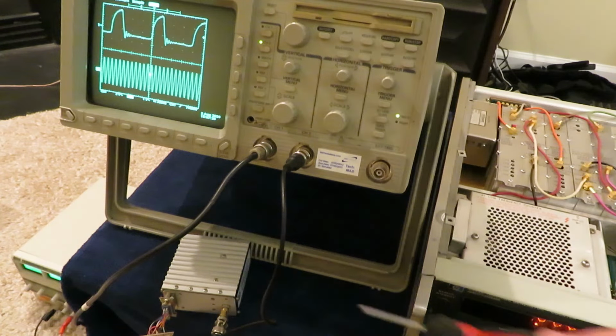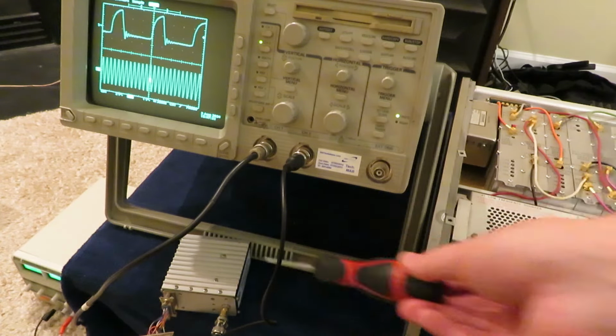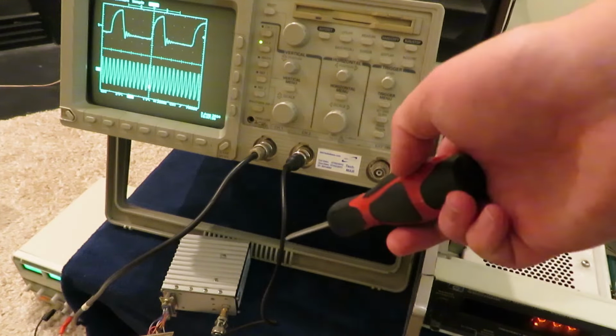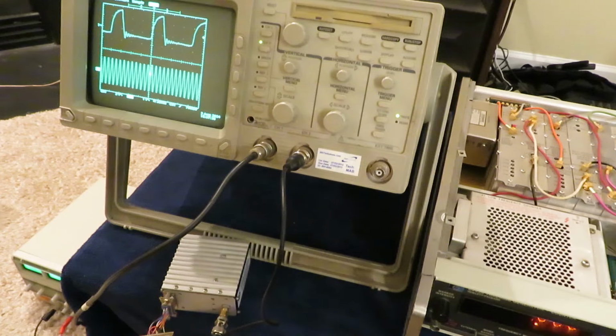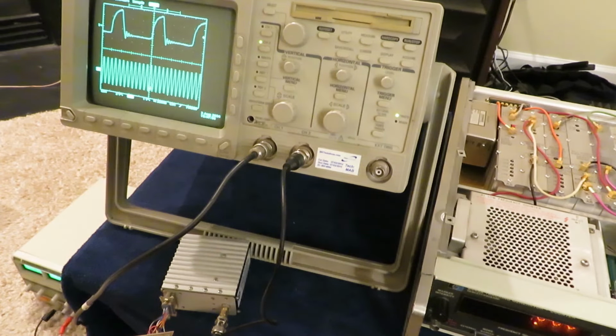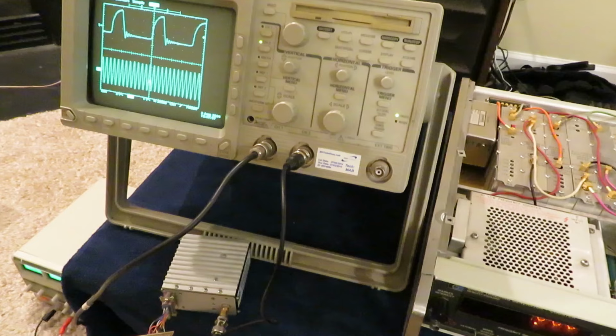You can see down here I have my rubidium reference, so both this unit and the rubidium reference have been running for several hours just to make sure they're warmed up and stabilized. The manual for the 8443 recommends that you leave the unit plugged in for 3 days continuously. I think that's a little bit overkill, but if you want to be really precise about it, that would be the amount of time to leave it on for.